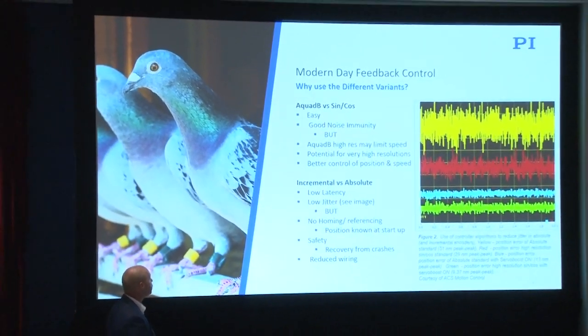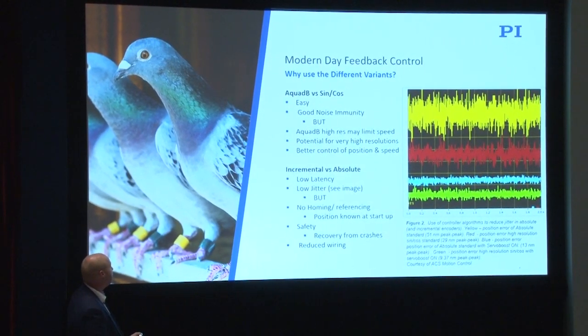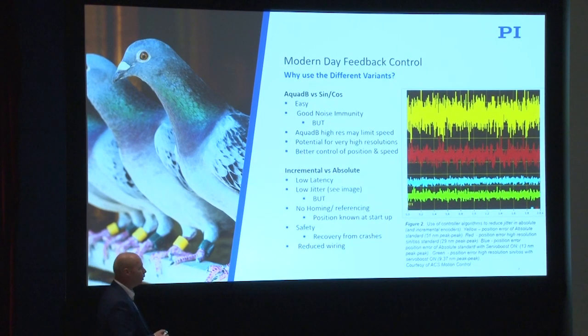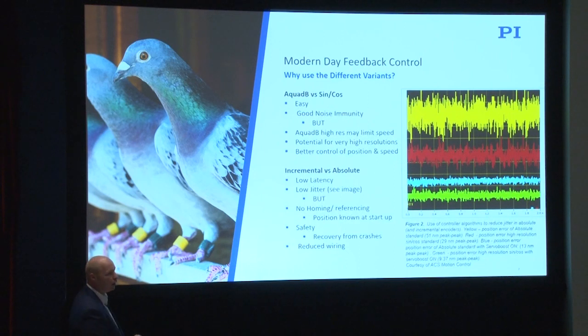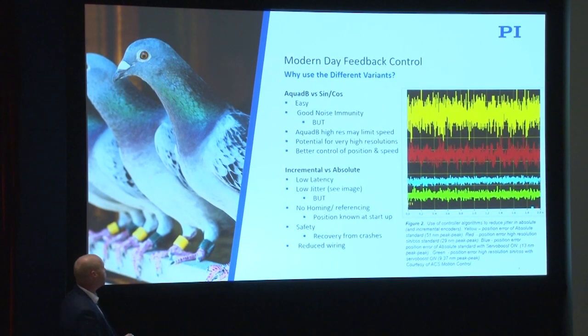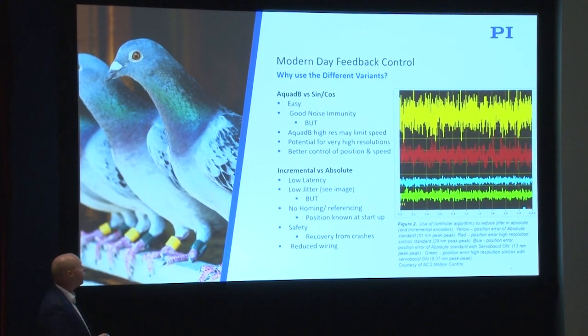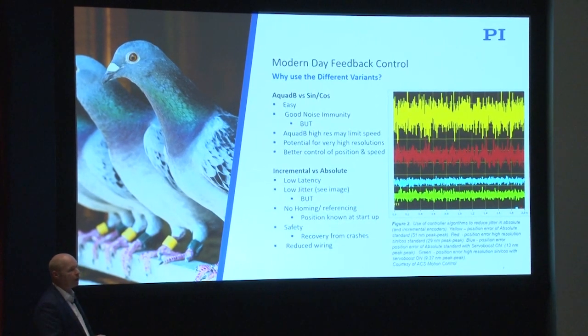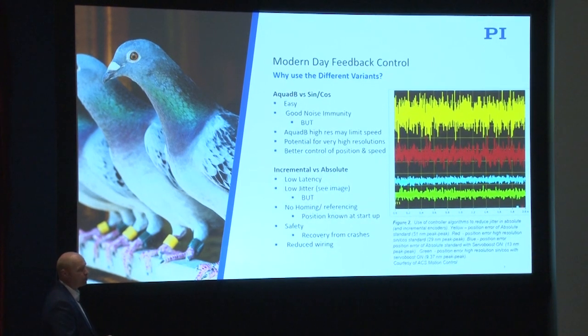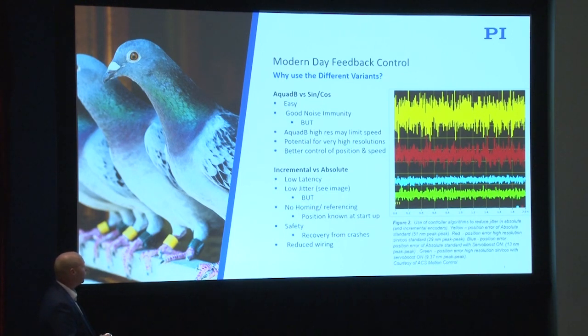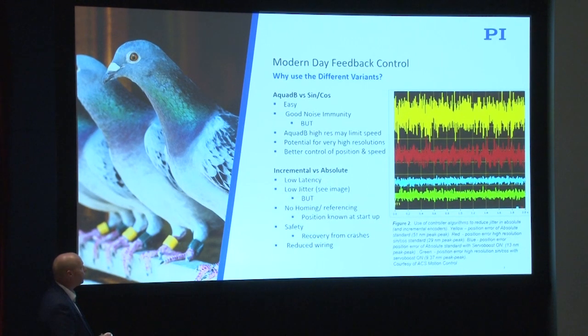So you've got the choice of A quad B versus sine cosine. Why would you use a sine cosine encoder? A quad B encoders have been around forever — they're easy and have really good noise immunity. But one of the things attractive about sine cosine is the potential for very high resolutions. With more information coming into the system, it's possible to get better control of position and speed, giving higher performance for precision motion systems.